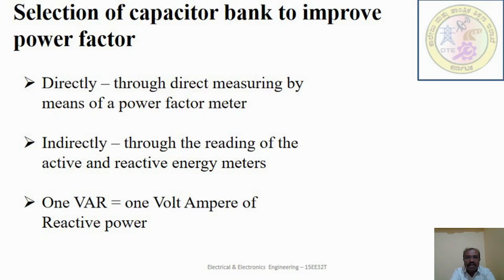This is to avoid the intake of excessive reactive energy, which is normally forbidden by the power supply authority. To carry out distributed or group power factor correction, it is necessary to calculate the cos phi of a single-phase load or a group of loads in factory areas.